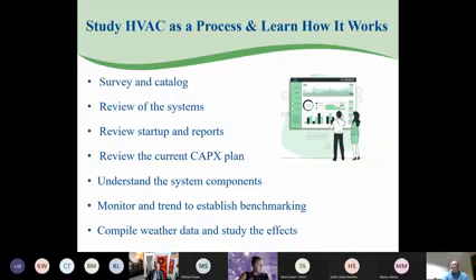So how do we learn our HVAC systems? We start out with surveying and cataloging the equipment, getting brands, models, serial numbers, collecting any and all data that can be used. We review all our drawings, design parameters, and OEM manuals of the systems to understand what the systems were designed to do. Review startup log sheets and any commissioning reports. If the systems were installed properly, the systems are or were the most efficient at the time of the commission startup. So reviewing those sheets will tell us how they compare.